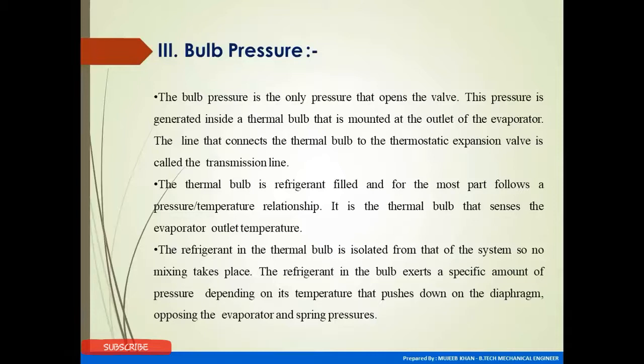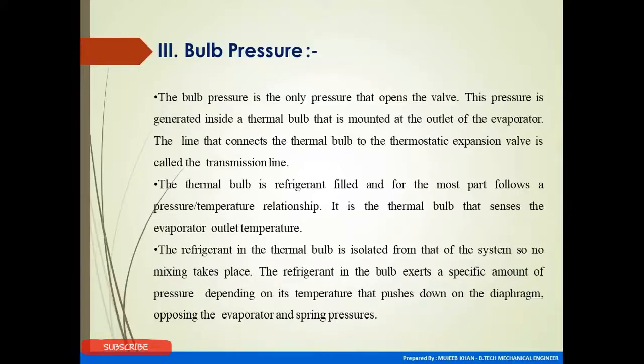Bulb pressure — let us see what bulb pressure is. The bulb pressure is the only pressure that opens the valve. This pressure is generated inside a thermal bulb that is mounted at the outlet of the evaporator. The line that connects the thermal bulb to the thermostatic expansion valve is called the transmission line. The thermal bulb is refrigerant-filled and follows a pressure-temperature relationship. The refrigerant in the thermal bulb is isolated from the system refrigerant, so there is no mixing. The refrigerant in the bulb exerts a specific pressure depending on its temperature, pushing down the diaphragm and opposing the evaporator and spring pressure.